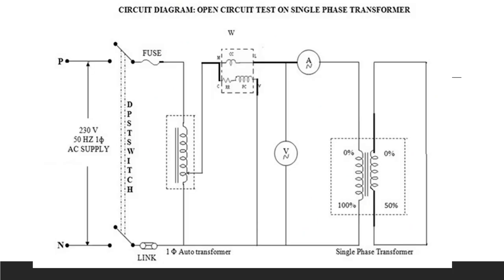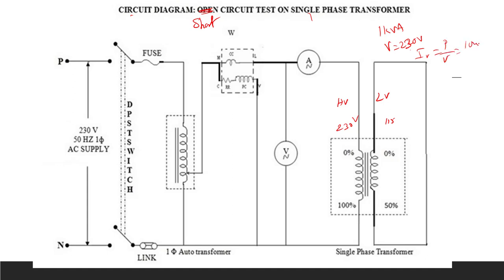This is the circuit diagram for the short circuit test on a single-phase transformer. The low voltage side has been short-circuited and the high voltage side is given the power supply. For a 1 kVA, 230/115 volt transformer, the rated current on the high voltage side will be IR = P/V = 1000/230 = 4.3 amps. So you have to set the rated current to 4.3 amps.